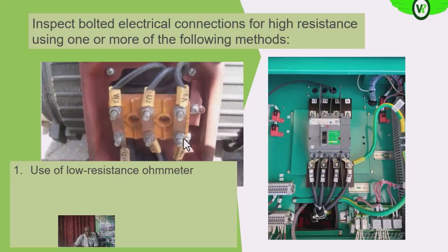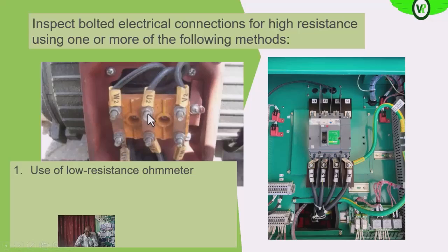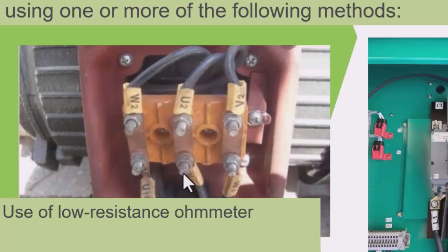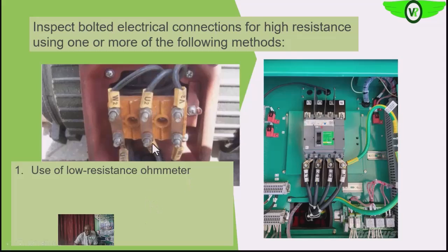So we can also use a low resistance meter to test the resistance at these terminal connection points. You see these cables, they are directly from the windings. Are we getting it? So we can place our low resistance meter probe here, and one here, to get the resistance between that lead and this terminal connection, or this shorting bar. That will give us an idea of the amount of resistance between this terminal lug and the shorting bar. So if it is beyond what is normal, because we expect it to be as close to zero as possible.